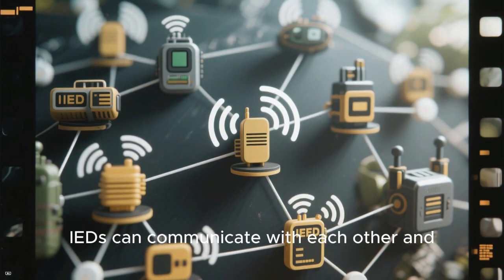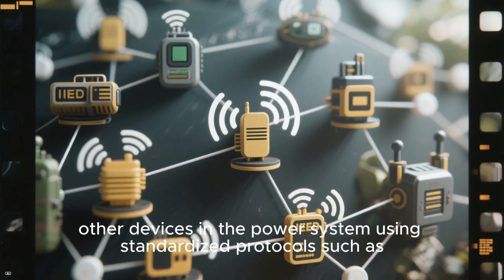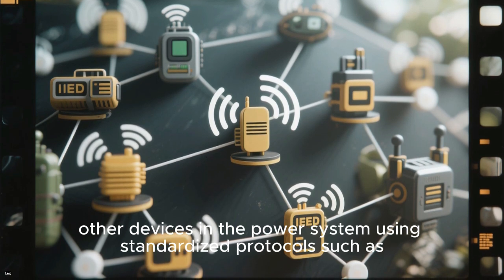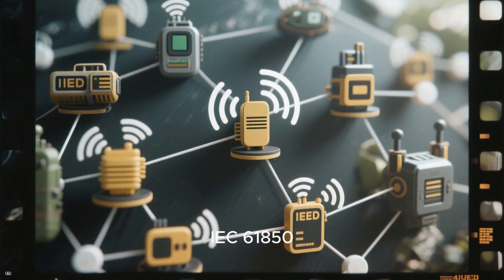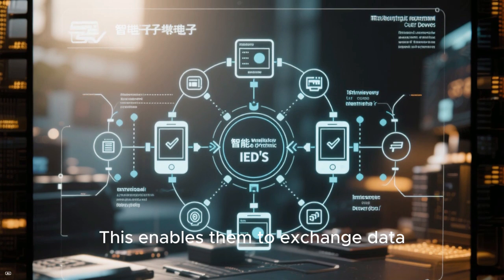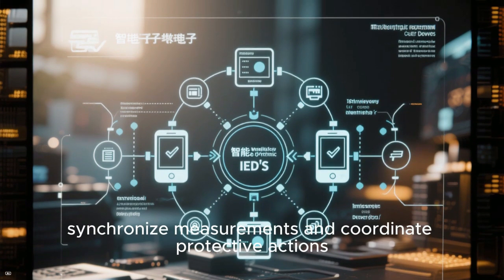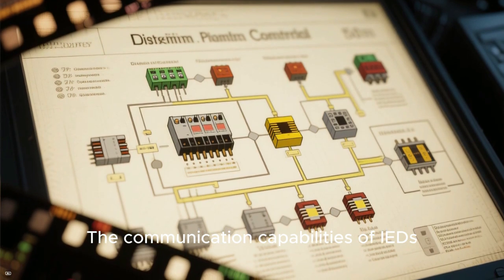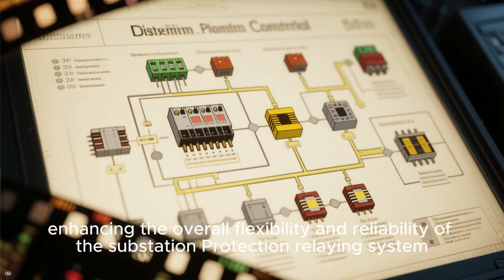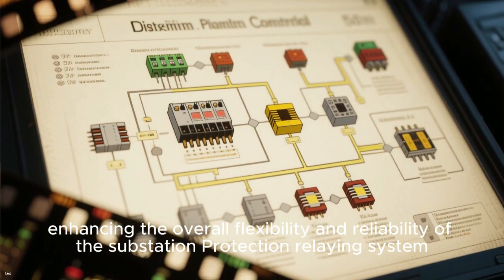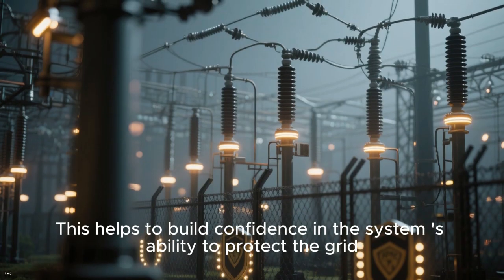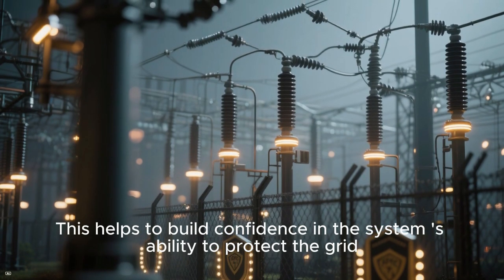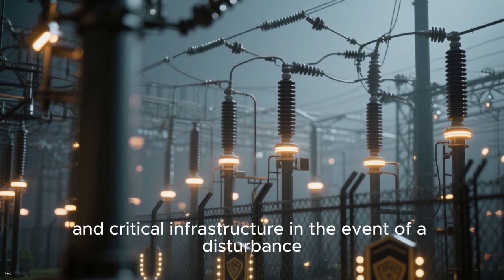IEDs can communicate with each other and other devices in the power system using standardized protocols such as IEC 61850. This enables them to exchange data, synchronize measurements, and coordinate protective actions. The communication capabilities of IEDs allow for the implementation of distributed control and protection schemes, enhancing the overall flexibility and reliability of the substation protection relaying system. This helps to build confidence in the system's ability to protect the grid and critical infrastructure in the event of a disturbance.